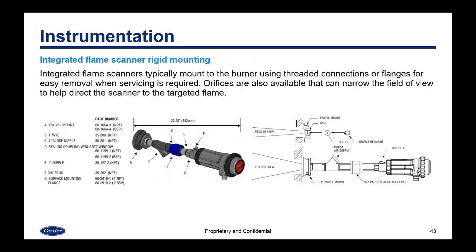An integrated flame scanner typically mounts to the burner using a threaded connection or flange so that it can be easily removed if servicing is required. You can also get an orifice which narrows the field of view to help the scanner see the targeted flame and not see any background noise or background flames. There's also a swivel or gimbal mount available so that you can position the scanner to aim in any direction and then tighten it down to maintain that position.